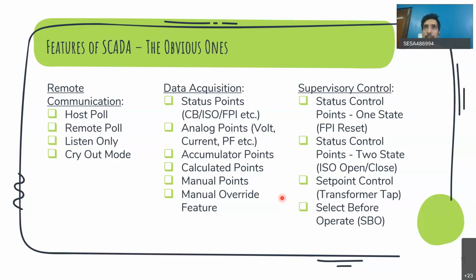So for example, because of some communication issue, your substation or RMU stops communicating, and during that time, something got tripped. So to mimic that exact field condition in the control center, you can manually change the status of that particular breaker in the control center. So you are manually overriding what is coming from field. Similarly, if there is something wrong with the equipment and it is giving you the reverse data by mistake, you can still manually override it when you know what is the right thing. So that is this feature. That is about data acquisition. Next is about supervisory control.